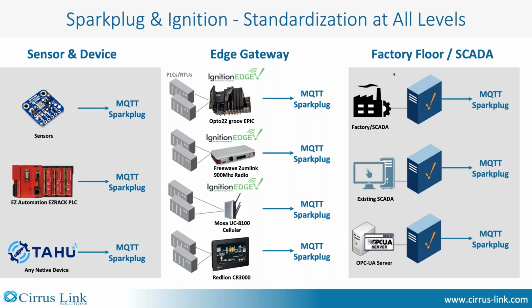For existing SCADA systems that are not Ignition, when you purchase the MQTT transmission module, it comes with the Ignition platform. This includes the OPC-UA server module, so that if most of your existing platforms support OPC-UA, you can connect all that data into Ignition, provide tag naming, and just with that one module, you can now push existing SCADA data into that enterprise.